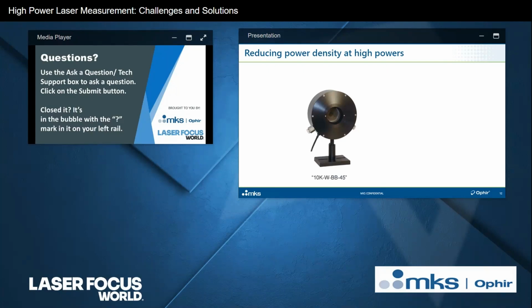So here you see a 10 kilowatt sensor. I hope you can see in the aperture of that sensor, there's a gold-coated reflective cone. And what we do here, I wish we could claim credit for this, but this trick is pretty much standard practice in our industry. Instead of the absorber just being a flat surface on which the beam is incident, and then we have those limitations of the damage threshold being pretty low because we're talking about high powers, what we do is we have the absorber as a vertical cylindrical wall around that reflective cone. And the reflective cone is where previously the absorber would have been for lower power sensors.